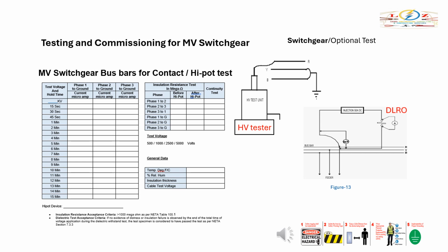Insulation resistance before and after high-pot test for bus bars of MV switchgear, but prior to that, on all bolted electrical connections, a contact resistance test must be done to compare values of similar connections. Investigate values which deviate from those of similar bolted connections by more than 50% of the lowest value, section 7.5.3.1.11.1. Bolt torque levels shall be in accordance with manufacturer's published data.